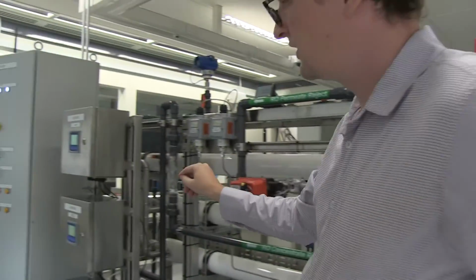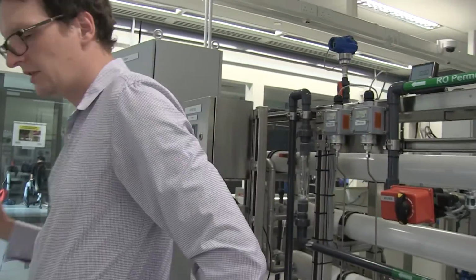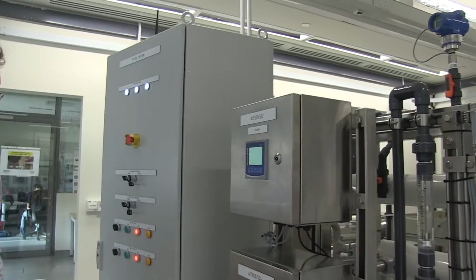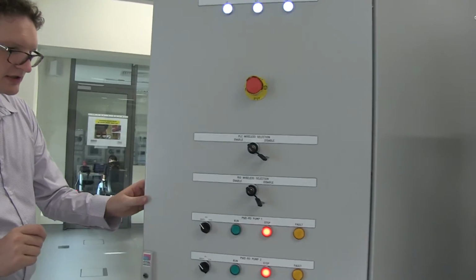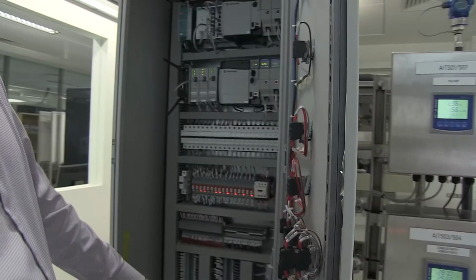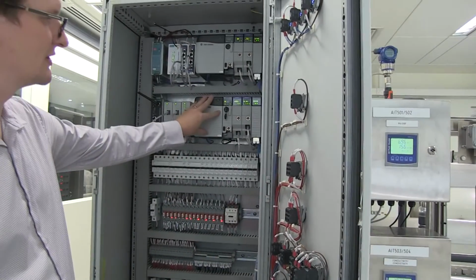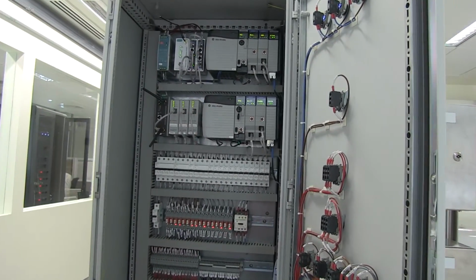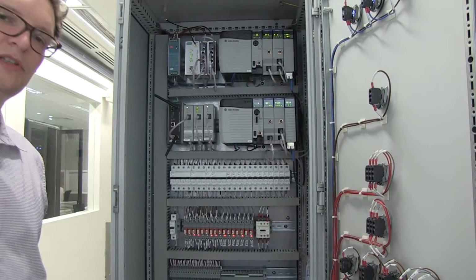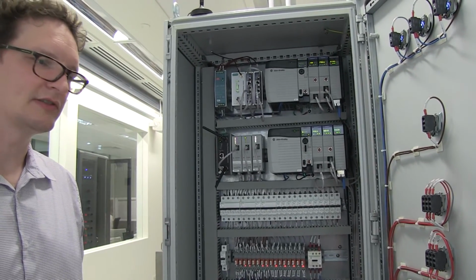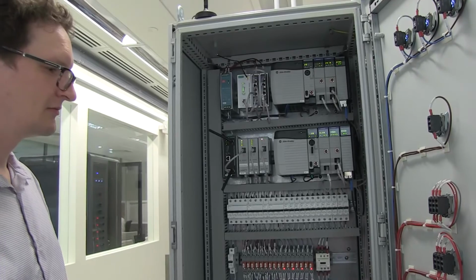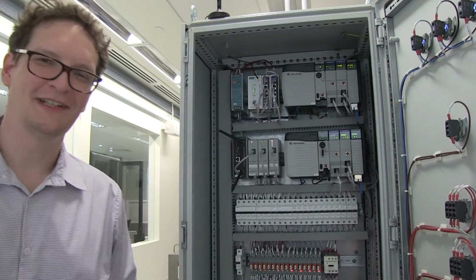and this current-based signal is essentially fed through this cable all the way to the housing, and in the housing it will be converted by the remote I/O unit into a digital value. This digital value is then supplied to the PLC, and the PLC bases its control decision on this value, and in addition the PLC will report this value to the historian and the SCADA system. That was a brief overview of the networking in SWaT.